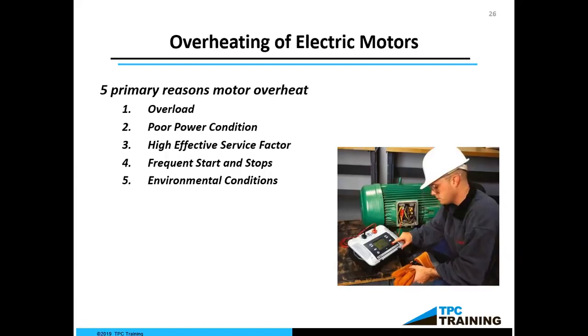So the overheating of motors, we can take care of that a little bit with thermal imaging, with our amp meter, sometimes even with our hands. Then you can see a poor power condition. So if we did have some power quality issues in the facility, that could cause some overheating. Those power quality issues could be low voltage, it could be harmonics, it could be transients. If we exceeded the parameter of the service factor, frequent starts and stops, environmental, all would cause overheating of that motor. So we got to keep our eyes and ears open to see what is going on with our motor.